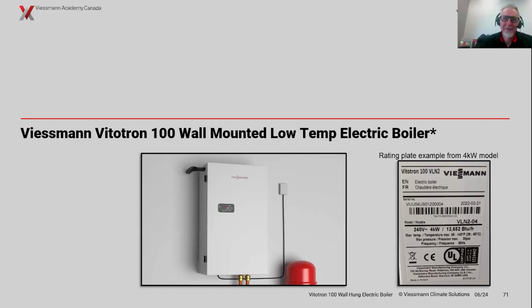Yeah, I did mention, see, this is why having the banter back and forth. Me mentioning glycol in the system sparks the question, can we run glycol through the system? Yes, you can put glycol in the system. We always recommend never more than 50%. You should only put as much glycol in the system as is absolutely necessary, as well as maintaining the pH levels on that glycol yearly.